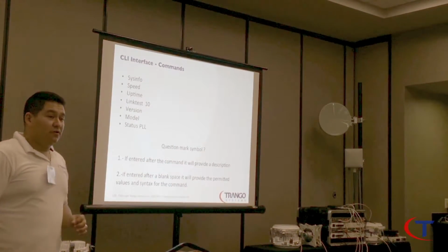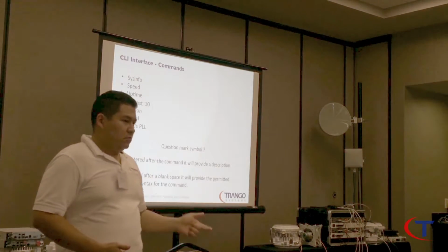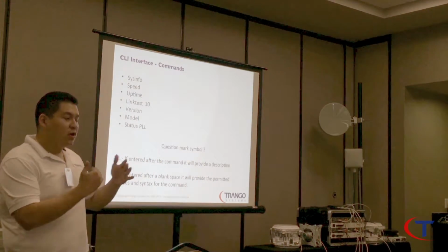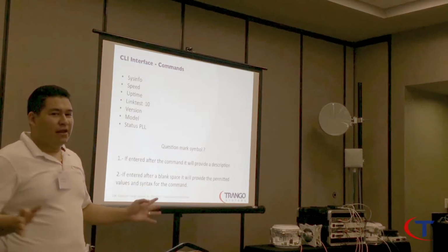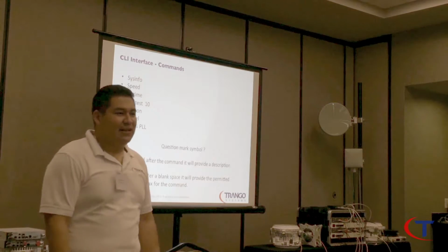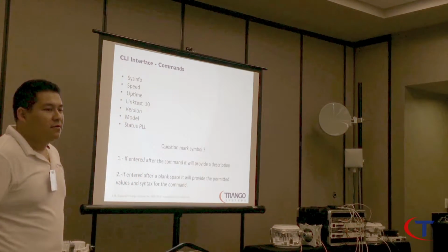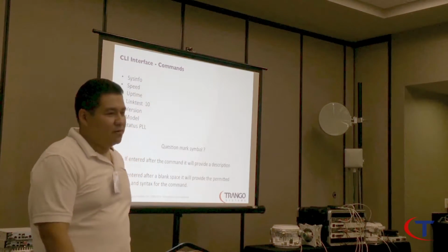Status PLL. If your link is up and running, the mode's on, the transmitter's on, and you do status PLL and they don't all come back at once, that's a failure automatically. That's a bad ODU. Is that basically just a low-level circuit board, are-you-there kind of thing? Correct. Pretty much, are you transmitting or not?